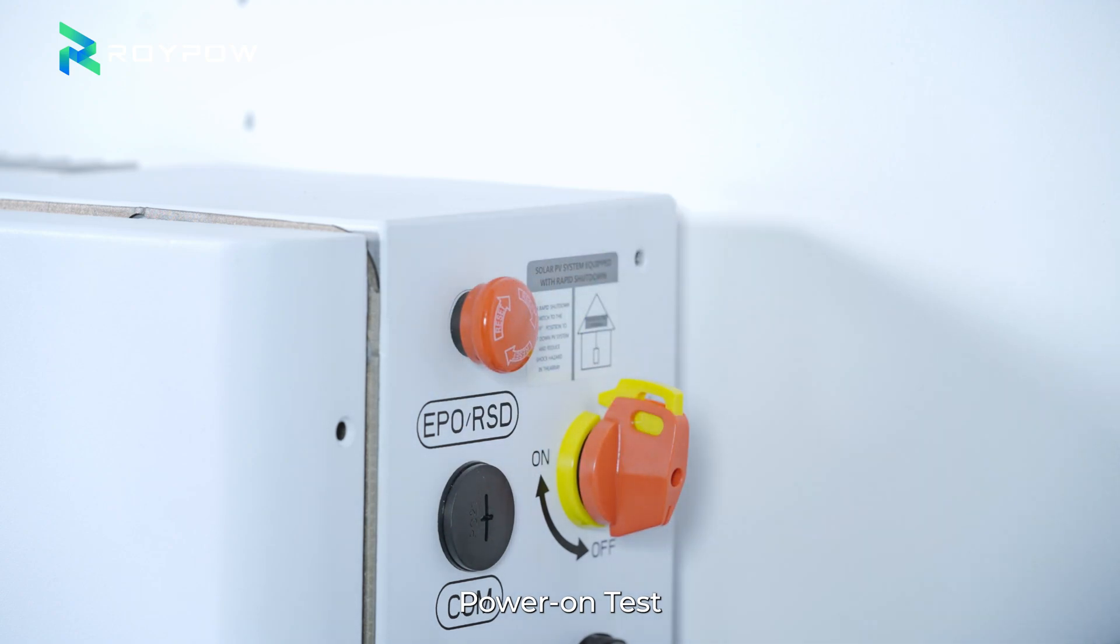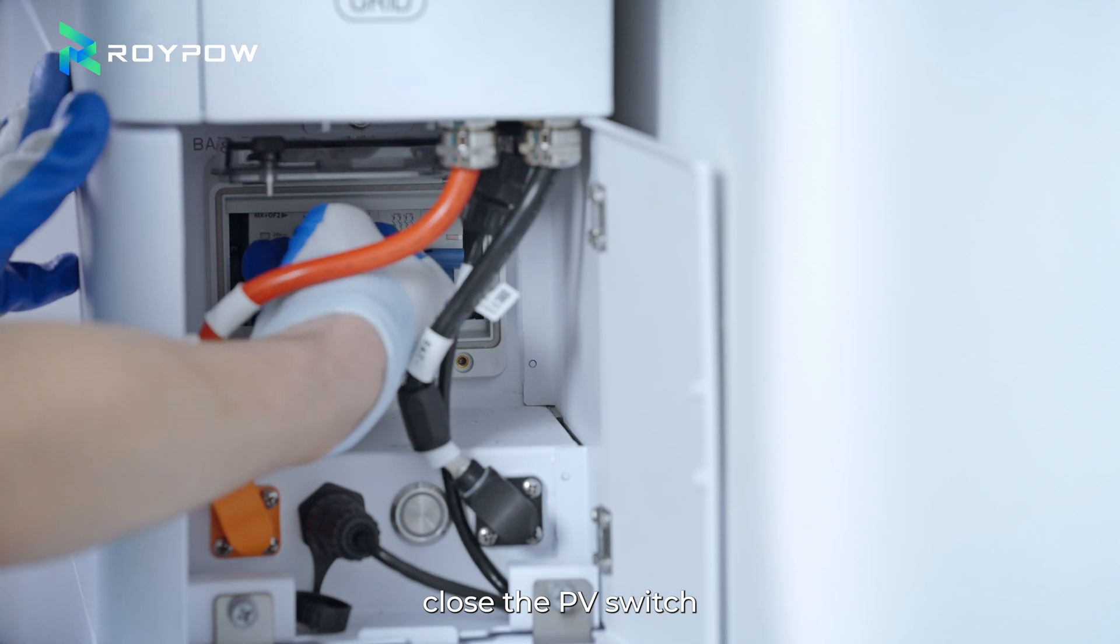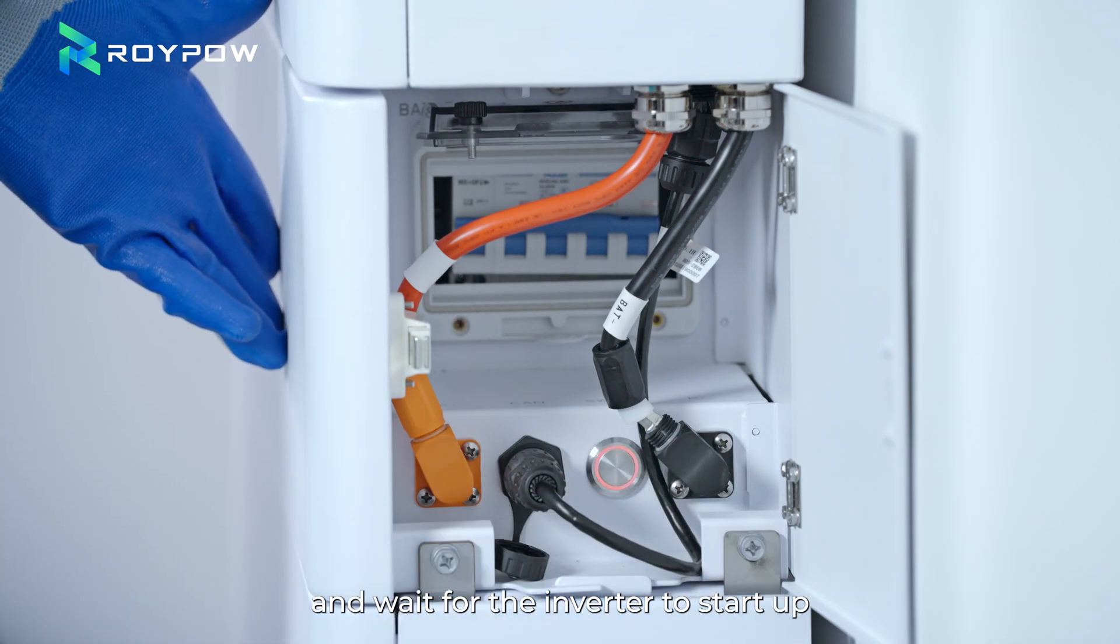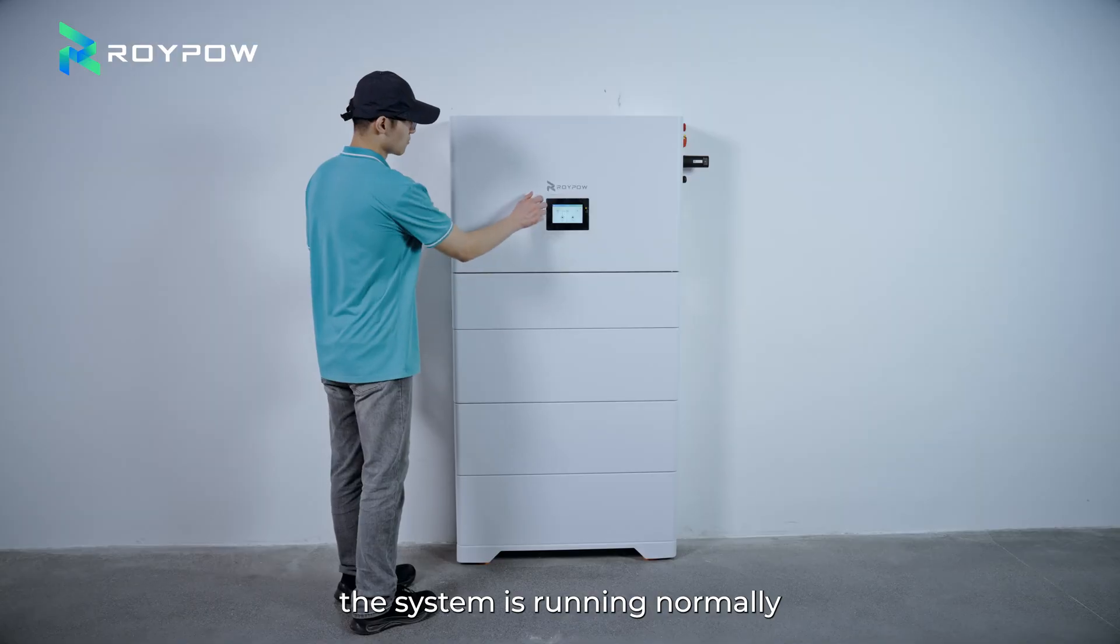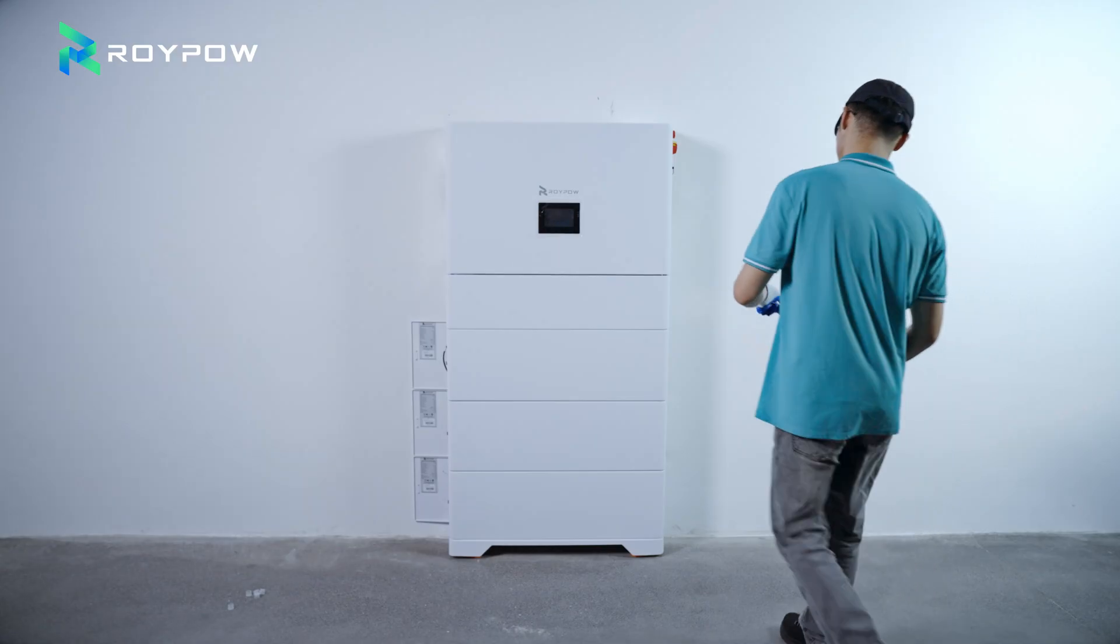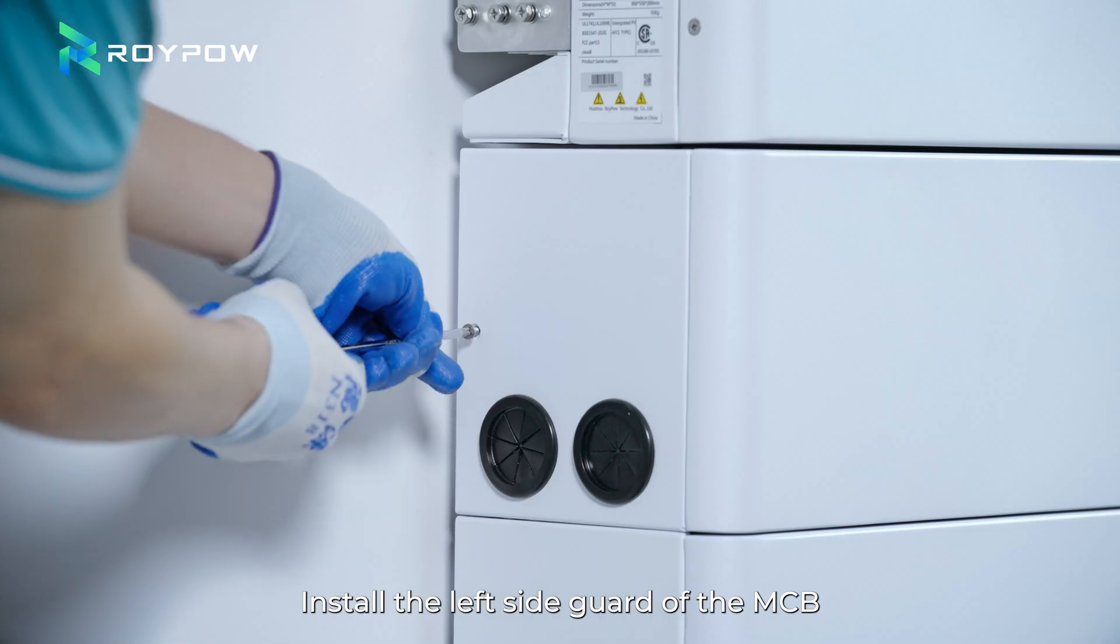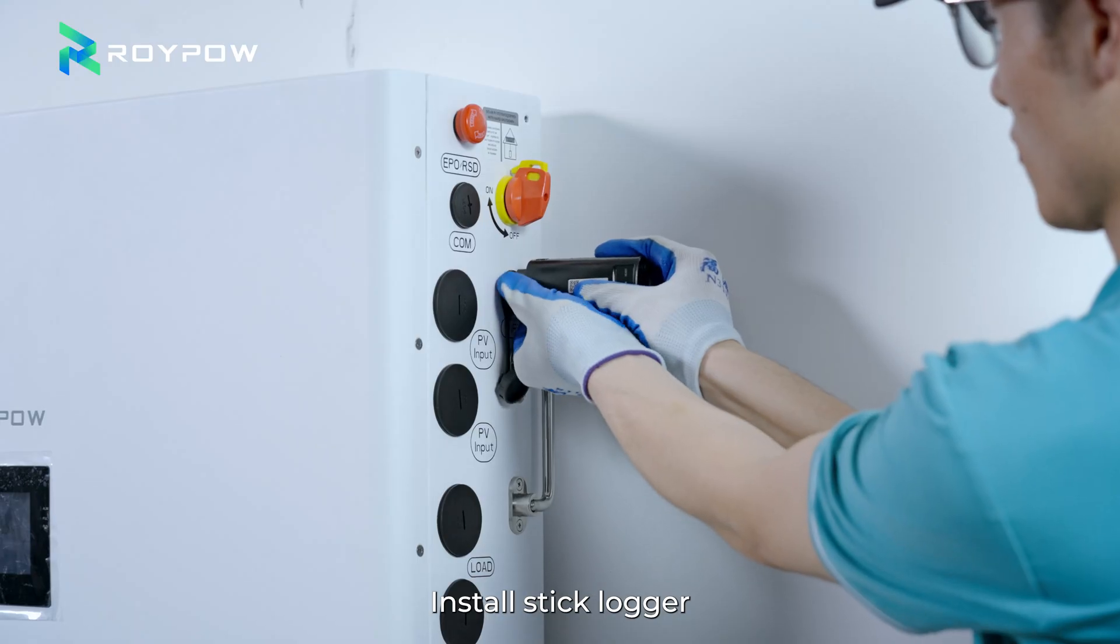Power on test. Release the emergency stop button clockwise, close the PV switch, close the circuit breaker, press the activation button for 5 seconds, and wait for the inverter to start up. When the screen lights up, the system is running normally. Install the right side cover of the battery. Install the left side guard of the MCB. Install stick logger.